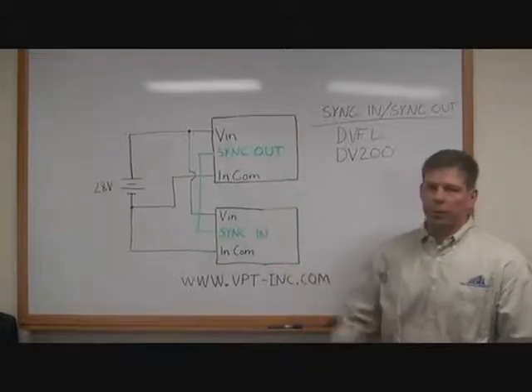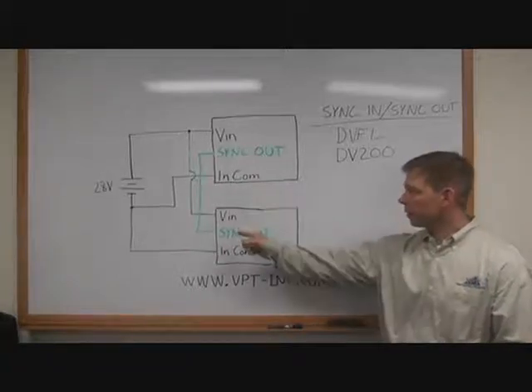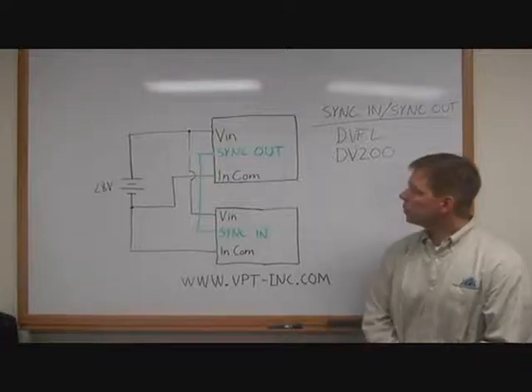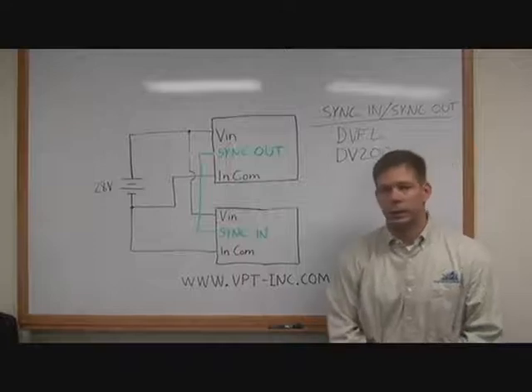One thing to remember, the sync signals on all of the converters, sync-in and sync-out, are referenced to the primary ground, so all grounding has to be referenced to the primary when hooking up the synchronization capability.